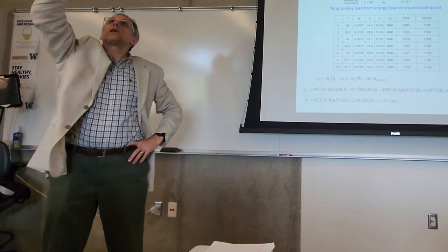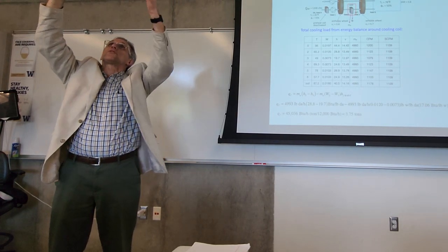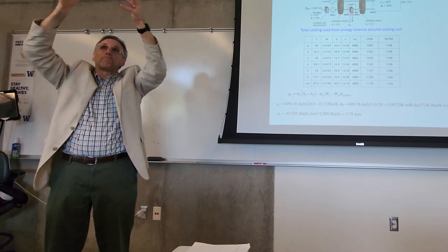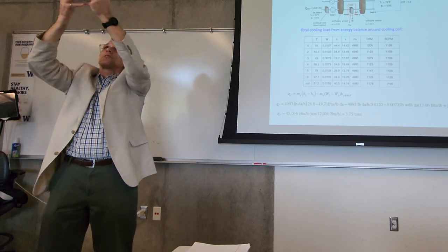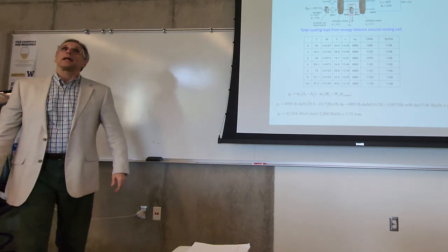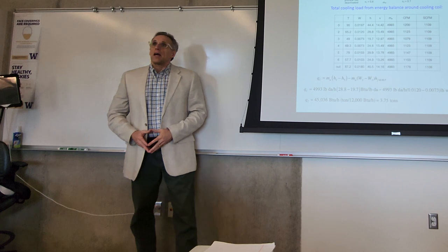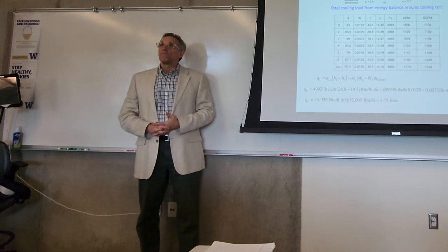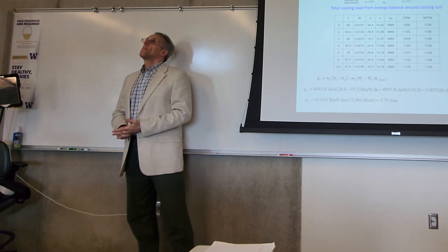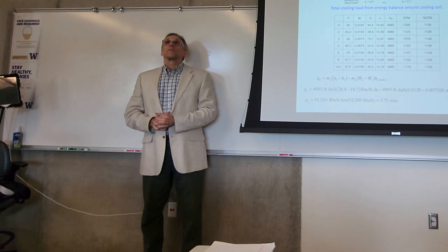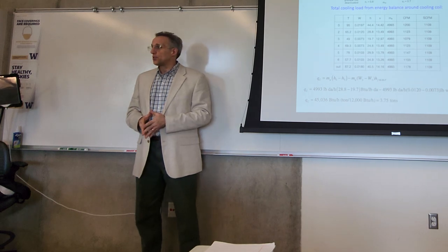Passive, yeah. So it's just cooling water, so the chilled water from the chiller plant is coming through and going through coils up here, and it's just relying on natural convection, the warm air comes up as that cool air falls down, and you get this little convective current going. And this is a nice way to get some cooling without having a fan dedicated to each room. So this would be a nice setup for adding a DOAS unit, because they actually do have ventilation issues in the summer.